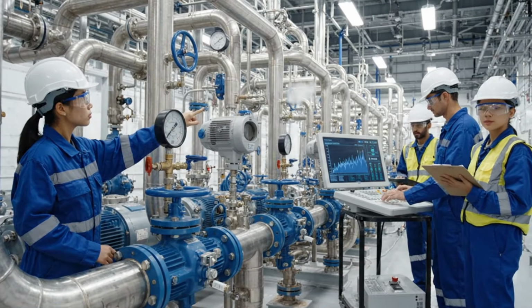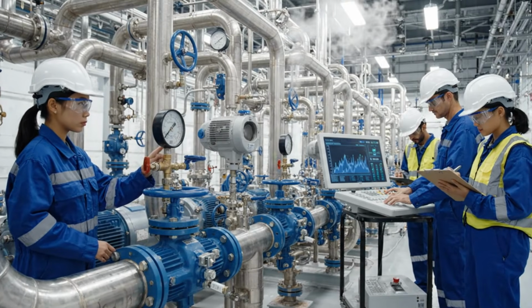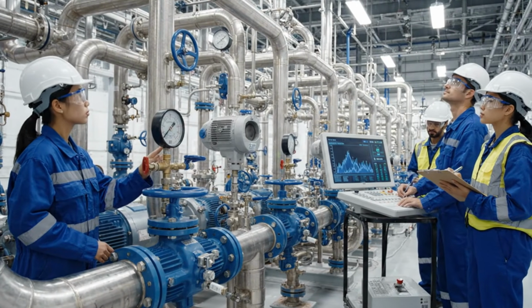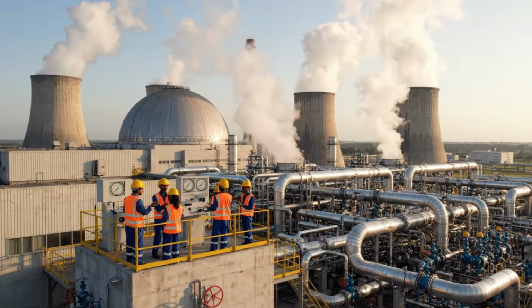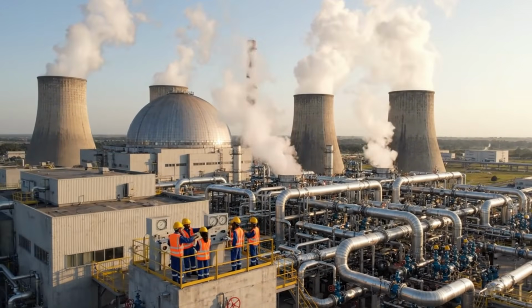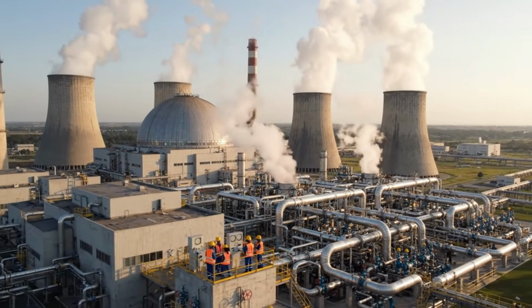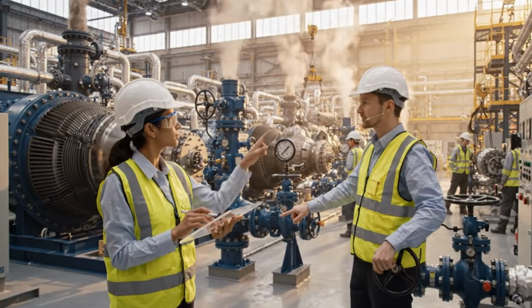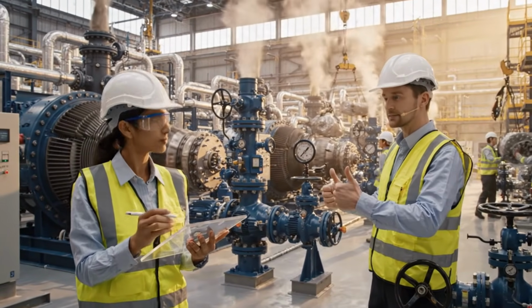Cold functional testing checks pumps, valves, electricity, and controls before systems reach operating temperature. Hot functional testing brings systems near operating temperature and pressure while fuel is still absent. Each test adds evidence that the real plant responds as the design predicted.